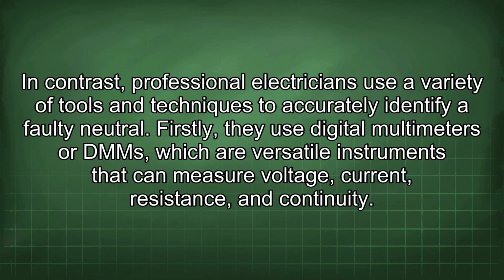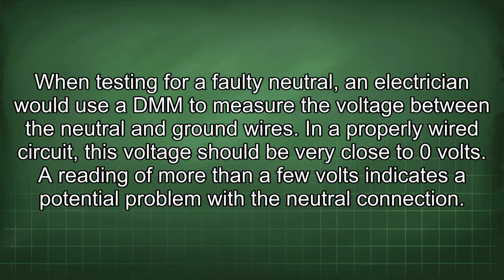Firstly, they use digital multimeters, or DMM, which are versatile instruments that can measure voltage, current, resistance, and continuity. When testing for a faulty neutral, an electrician would use a DMM to measure the voltage between the neutral and ground wires. In a properly wired circuit, this voltage should be very close to 0 volts. A reading of more than a few volts indicates a potential problem with the neutral connection.